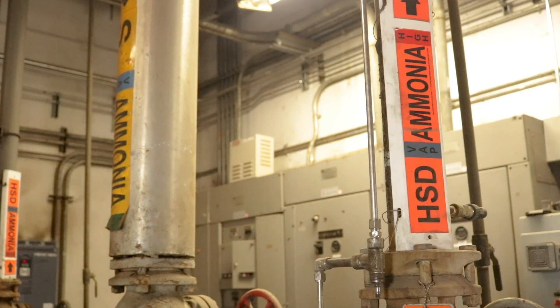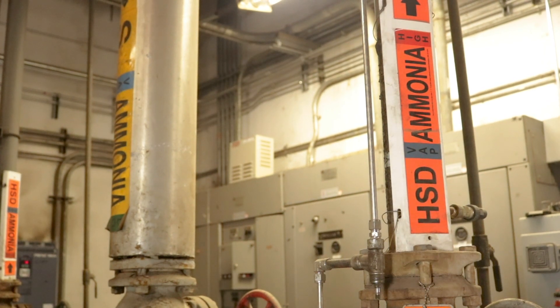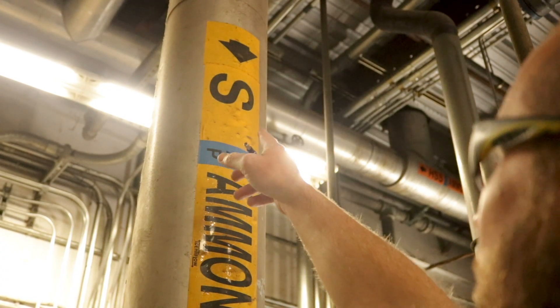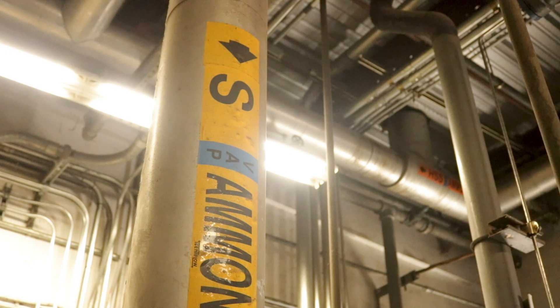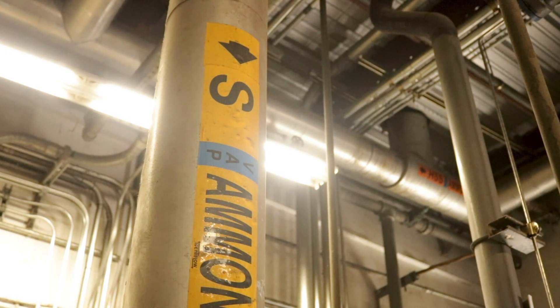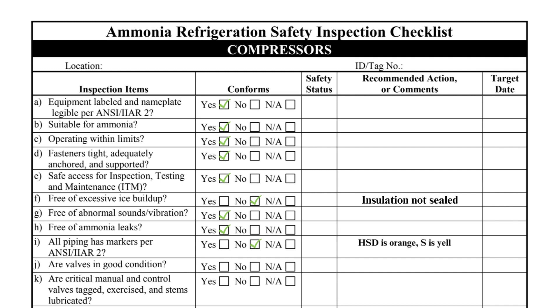This compressor has an orange label on the high-stage discharge pipe and a yellow label on the suction. Furthermore, the suction pipe abbreviation is simply "S." IIAR Standard 2 Appendix Q recommends that the pipe service abbreviation be "HSD" for this application.